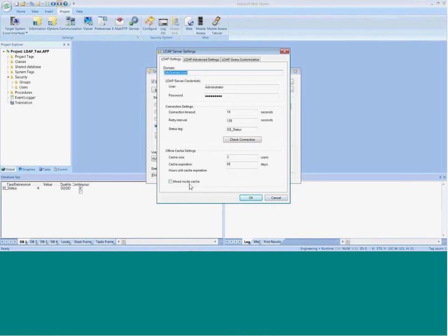One of the things I'd like to, actually two things, I'm going to offshoot on that, because I always suggest that before you configure a security system in your project, you make a backup of your project. When I teach training classes, before we do the security system and before we configure multiple languages, I highly recommend people back up their project, because with multiple languages and with security system, I've seen people either change their language and can't get back, or lock themselves out of the security system, and it's always a good idea to make a backup before you do that. So that's item number 1.